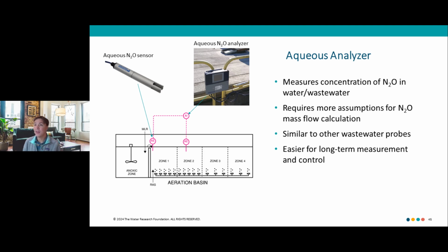As Emma mentioned, the only analyzer that's available as an aqueous probe is the Unisense Clark type probe, electrochemical probe. We installed 2 probes and the controller. The first probe we located just downstream of the anoxic zone where the flow falls over a weir into the aerated zone. We couldn't access the anoxic zone directly from above, so that was the closest point where we thought we could sample to get a representative concentration of nitrous oxide in the mixed liquor from the anoxic zone. The second probe we located in our second aeration zone, about a third of the way down the aeration basin.